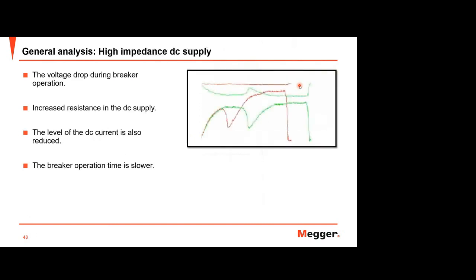Okay, and then regarding high impedance DC supply, from this picture you can see the record shows the voltage drop, the green one, during breaker operation. This is caused by increased resistance in the DC supply of the breaker. So you can see the latching coil operation time here increase. When the coil operation increases, the main contact also will increase. So you can see the comparison between the red one and the green one. This gives you a longer operation time of the circuit breaker. So you need to investigate what caused this issue. Probably some connection or issue on the battery circuit.